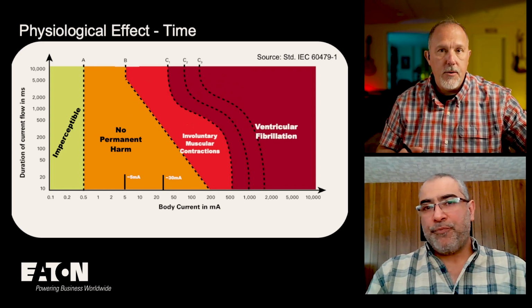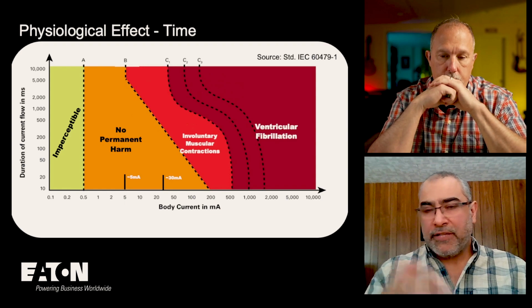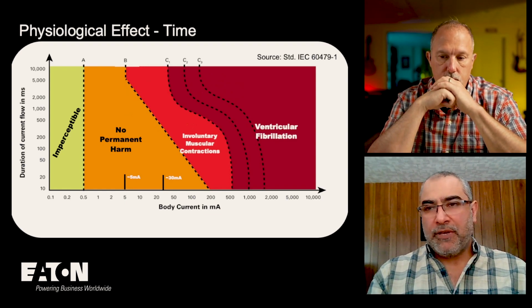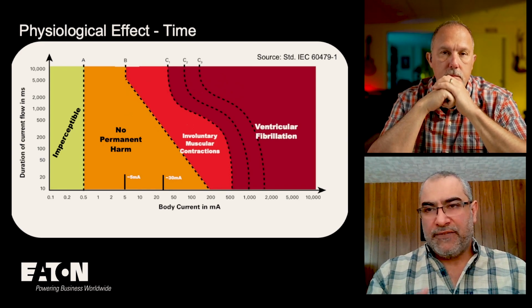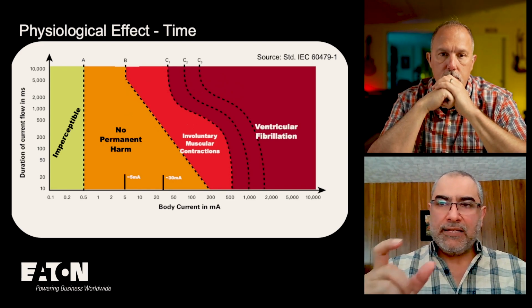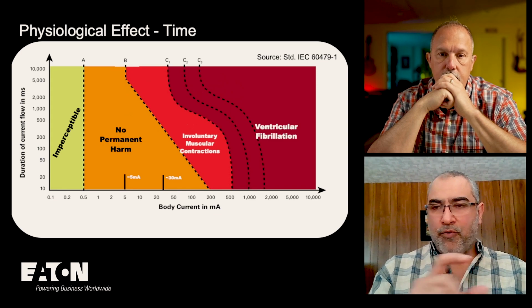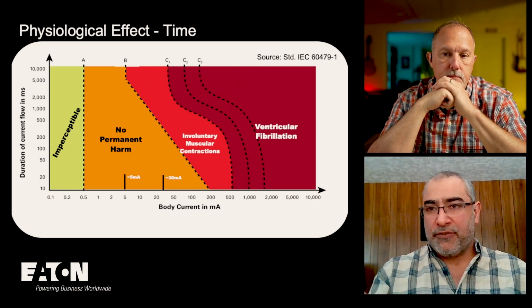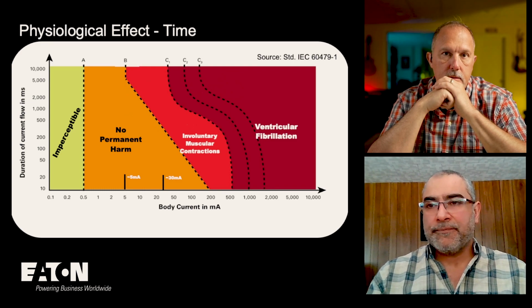This is a very good point, because the GFCI UL 943 standard has a curve, and the equation - the time current characteristics of GFCIs - is essentially what you're just describing. It's an inverse current curve.